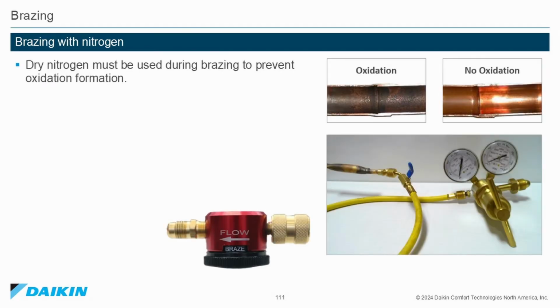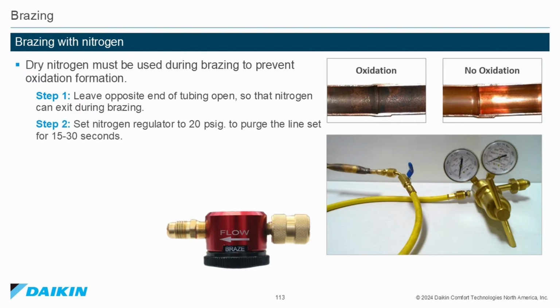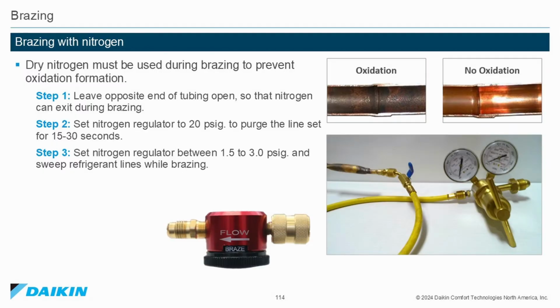Brazing with nitrogen. Dry nitrogen must be used during brazing to prevent oxidation formation. Step 1. Leave the opposite end of the tubing open so that the nitrogen can exit during brazing. Step 2. Set the nitrogen regulator to 20 psig to purge the line set for 15 to 30 seconds. Step 3. Set the nitrogen regulator between 1.5 and 3 psi and sweep the refrigerant lines while brazing.